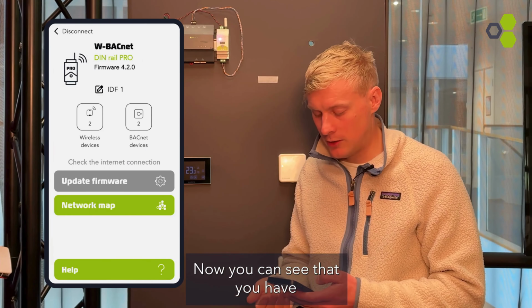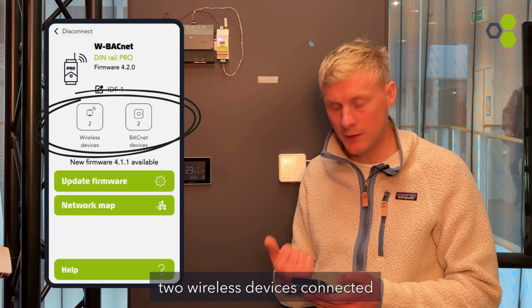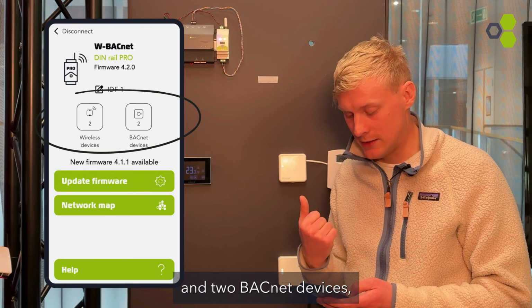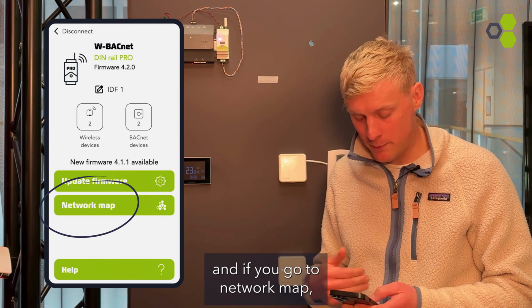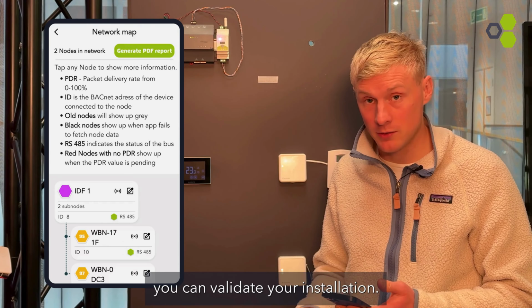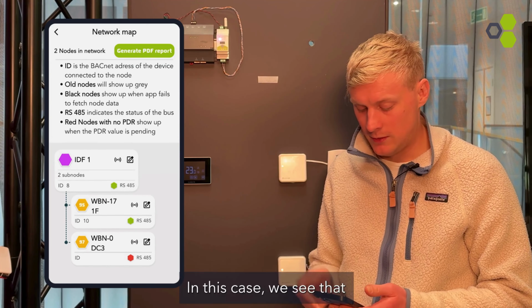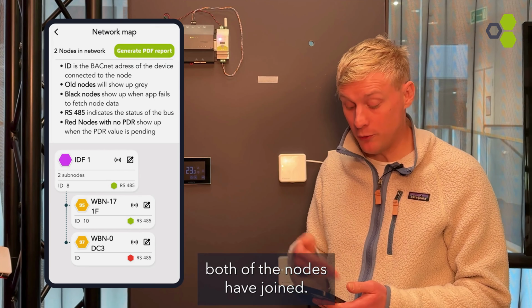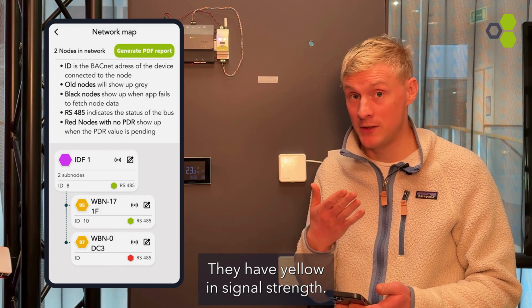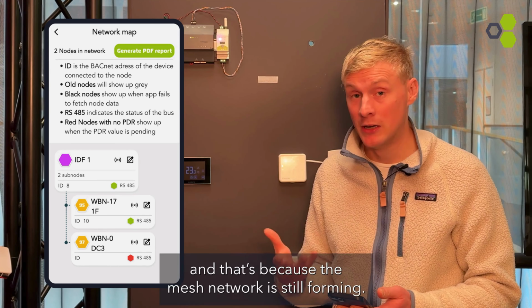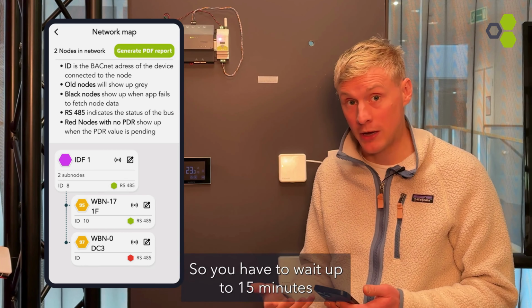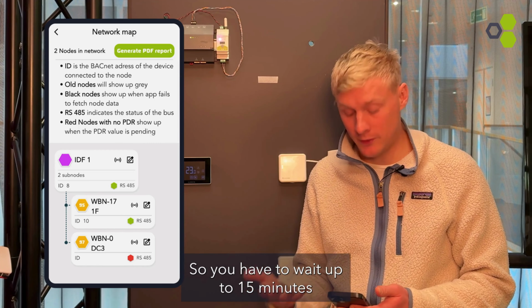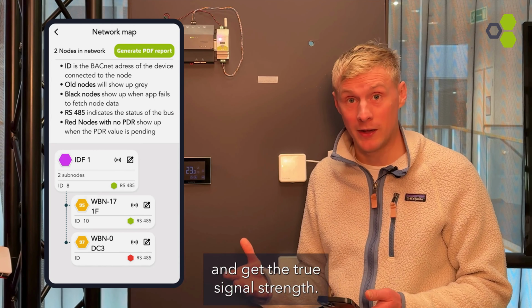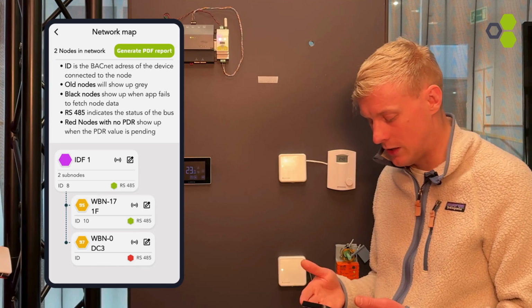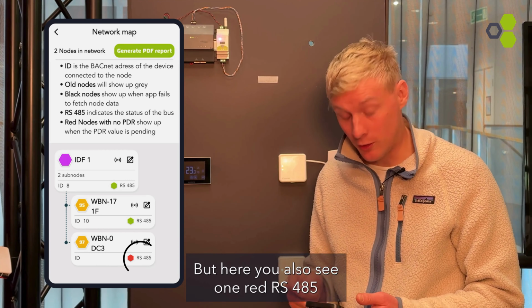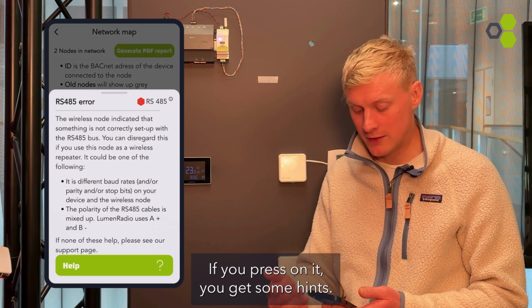Now you can see that you have 2 wireless devices connected and 2 BACnet devices. And if you go to network map, you can validate your installation. In this case, we see that both of the nodes have joined. They have yellow in signal strength, and that's because the mesh network is still forming. So you have to wait up to 15 minutes in order for it to form completely and get the true signal strength, so to say. But here you also see one red RS485. If you press on it, you get some hints.